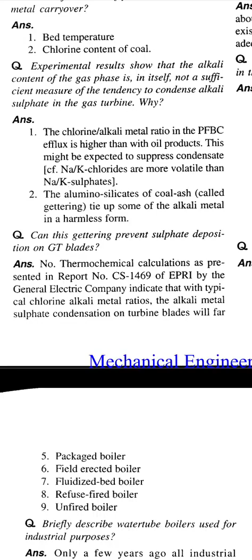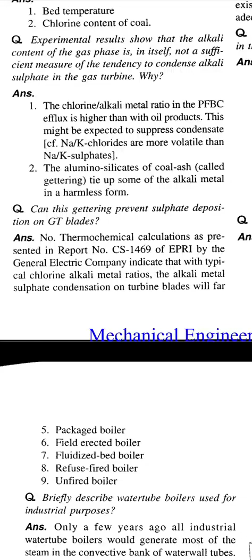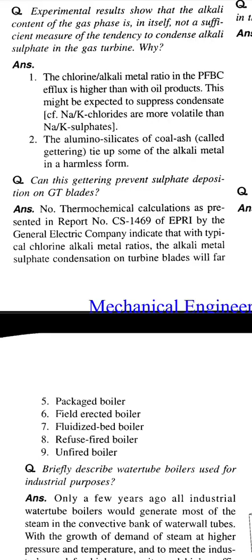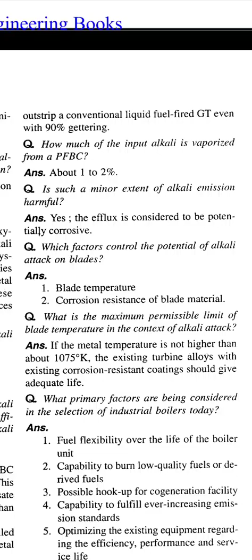Second, the aluminosilicates of coal ash, called gettering, tie up some of the alkali metal in harmless form. Question: can this gathering prevent sulfate deposition on GT blades? Answer is no. Thermochemical calculations, as presented in EPRI report number CS1469 by the General Electric Company, indicate that with typical chlorine to alkali metal ratios, the alkali metal sulfate condensation on turbine blades will far outstrip a conventional liquid fuel fired GT, even with 90% gettering.